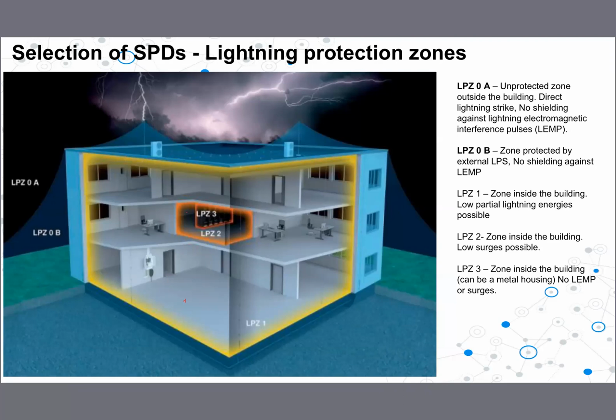From there to the earth pit, definitely you can, because we size the earth cable accordingly. I explained in the presentation, if it is type 1, we use 16. If it is type 2, 4 millimeters is also enough. So this cable should be less than 50. The rest of the earthing system we decide on other factors, short circuit current and other things, taking into consideration other electrical design aspects as well. Based on that only we decide. So this part only we need to limit to 50 centimeters.